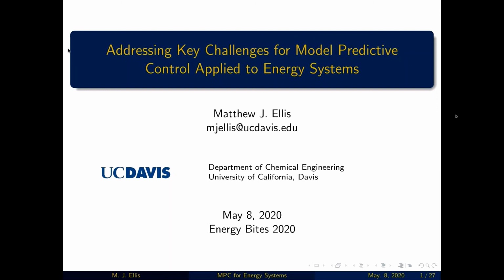Good question. In the screen we show for the central plant optimization product, we actually forecast 7 days in advance. We do 7 days to account for at least the upcoming weekend being included in that forecast. In terms of scheduling, the equipment is scheduled automatically by the MPC, so the user doesn't have to interfere. If the user knows equipment is going to be down for routine maintenance, they can schedule that in the system, and it will automatically account for that in the control.